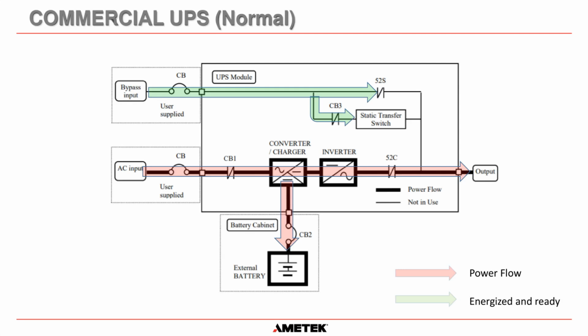Okay, so as you can see here, we have the red power flow. That is the normal power flow, and the green is energized and ready. So in a commercial UPS, power flows from the AC input through the CB1 input breaker into the charger. The charger trickle charges the battery, and then the DC goes all the way through the inverter, through 52C contactor, and out to your critical loads. Okay. Oh, not enough room for me to write in there. And then our bypass supply is ready at this contactor here, and it's ready at the static switch, but we haven't turned it on. It's just waiting just in case the output of the inverter fails, and then it's ready to supply power.